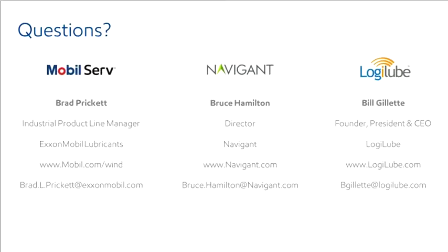Yeah, it's great. Thanks, listener, for that question. Excellent question, by the way, and there is a direct parallel and correlation between, let's say, a wind turbine gearbox that we just referenced in the presentation, and a gearbox used in an industrial setting, possibly at a mineral processing site on a copper, iron ore, or gold ore, where you might be taking 3 to 6,000 electric horsepower to actually drive a pinion gear to rotate a grinding mill. There would be a multi-stage gearbox that takes the input RPM and reduces it down to 20, 30 RPM to drive the pinion.